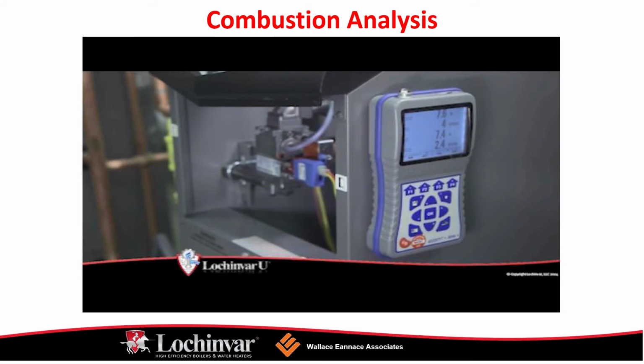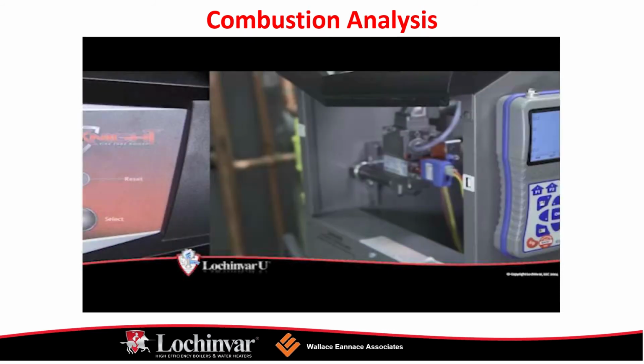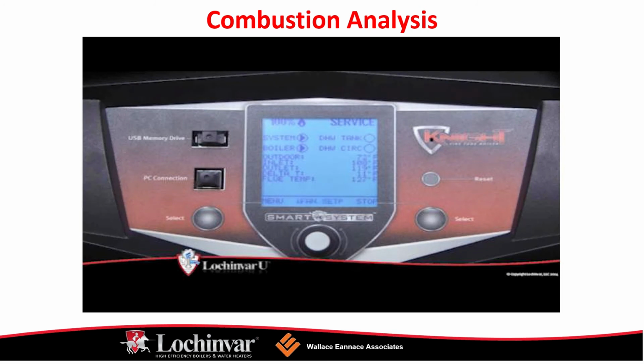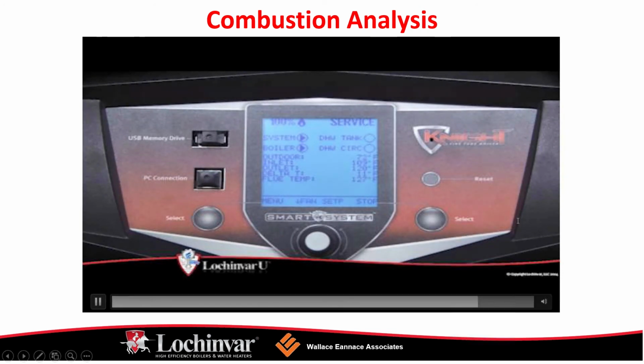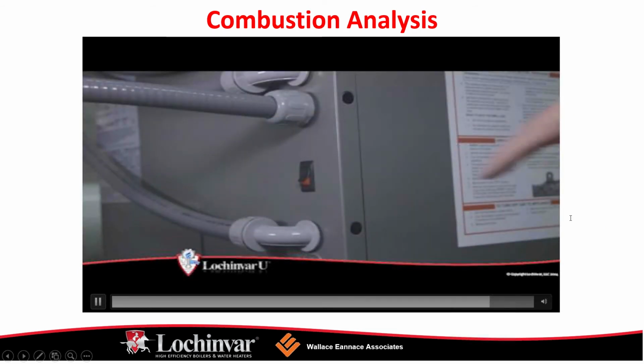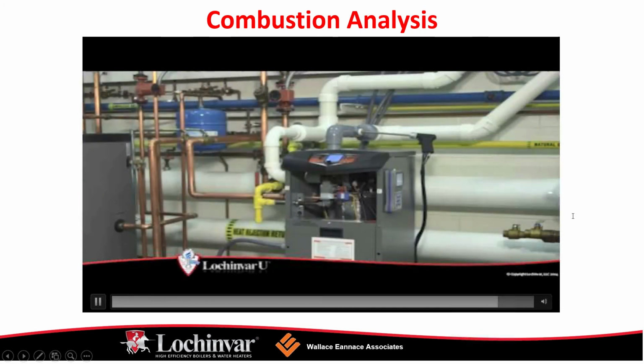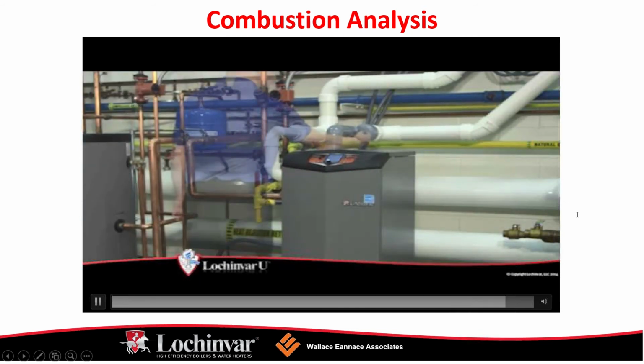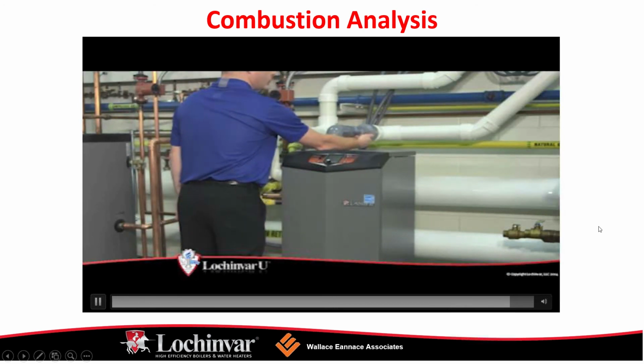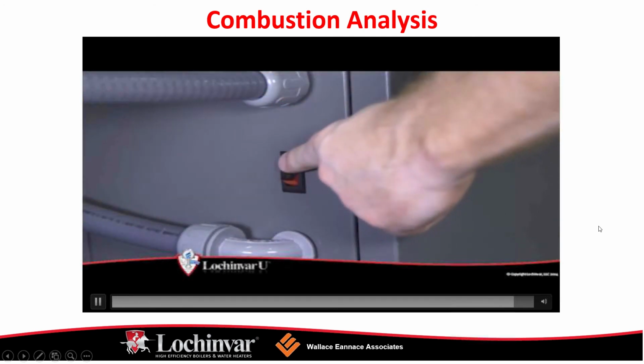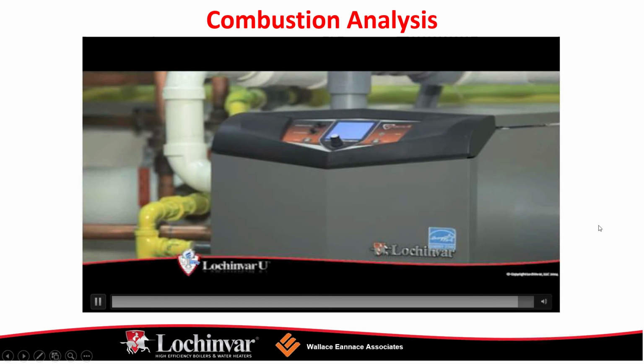Refer to the video, How to Measure Inlet Gas Pressure, to determine if an adequate gas pressure has been delivered to the unit. Refer to the video, Burner Removal and Cleaning, to determine if the burner is damaged or is in need of cleaning. Refer to the video, Heat Exchanger Access and Cleaning, to determine if the heat exchanger is in need of cleaning. If the combustion levels are still not within the specified ranges after reviewing the possible causes, adjustment of the gas valve may be necessary.